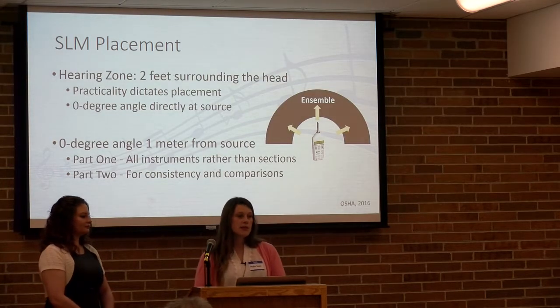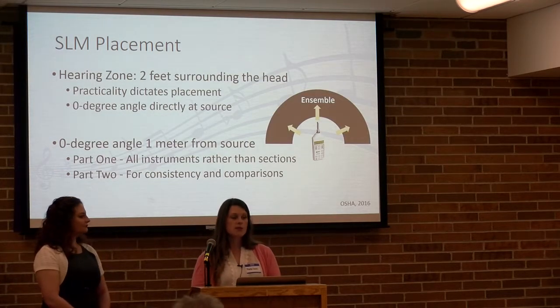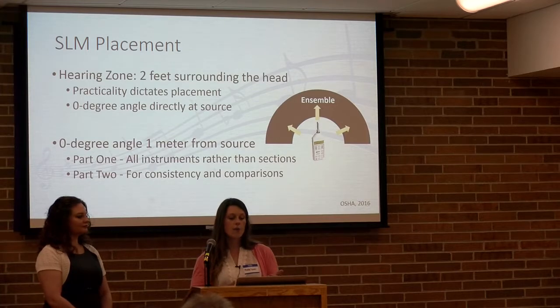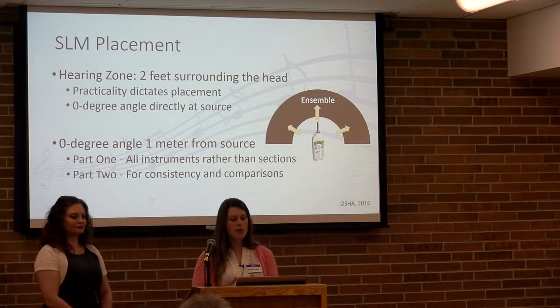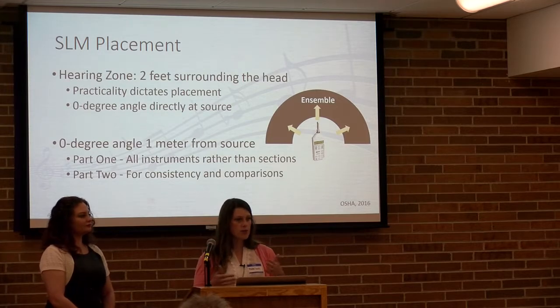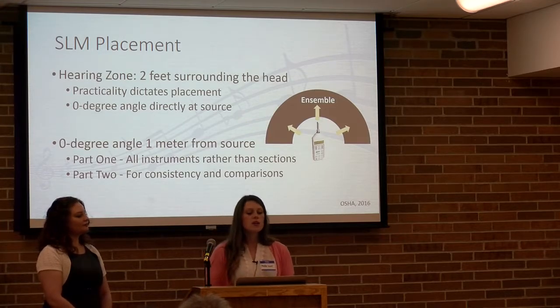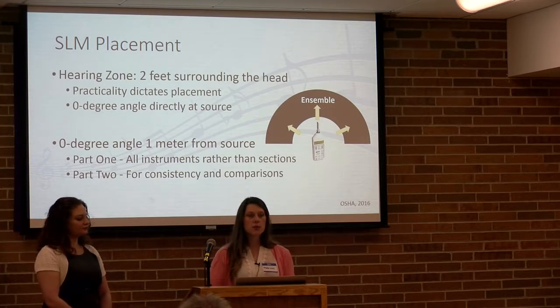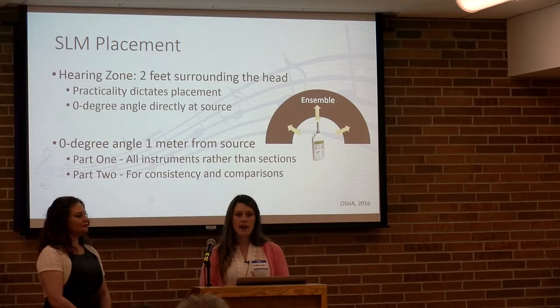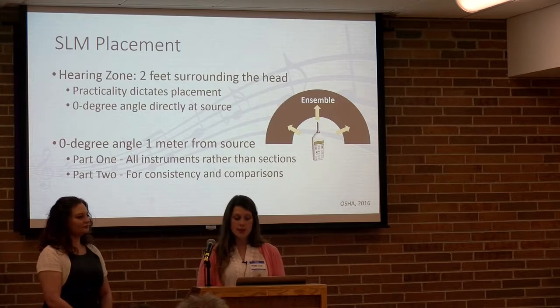For the sound level meter placement, I used OSHA guidelines because I used a free field microphone that's a handheld on a tripod. And OSHA has more guidelines on how to use a sound level meter like this, whereas NIOSH uses more of a dosimeter, which is clipped to an individual. OSHA defines hearing zone as within 2 feet of the individual's head. But they do say that practicality and environmental factors need to dictate your placement.